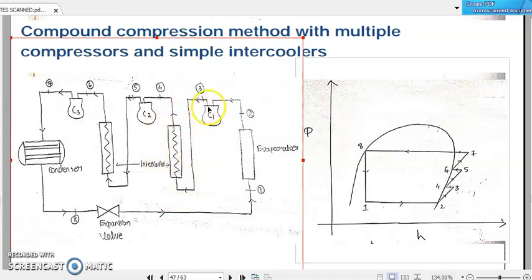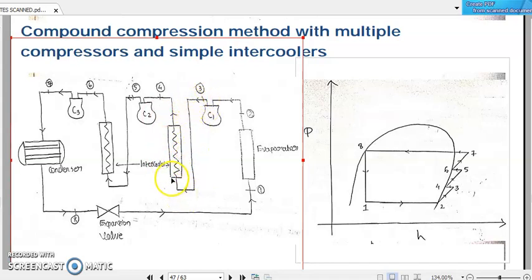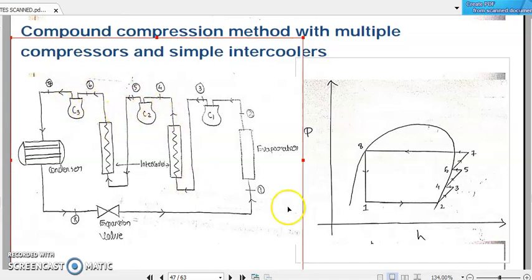What is happening inside the intercooler is the refrigerant coming out from C1 will be passed through the intercooler before it enters the second compressor C2. In this intercooler, the refrigerant rejects a partial amount of its heat to the cooler medium, and only after that it enters C2. The same thing happens between C2 and C3 as well. That is what we mean by intercooling or intermediate cooling happening between two consecutive stages of compressors.